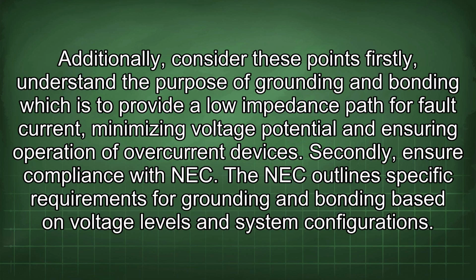Additionally, consider these points. Firstly, understand the purpose of grounding and bonding, which is to provide a low impedance path for fault current, minimizing voltage potential and ensuring operation of overcurrent devices. Secondly, ensure compliance with NEC. The NEC outlines specific requirements for grounding and bonding based on voltage levels and system configurations.